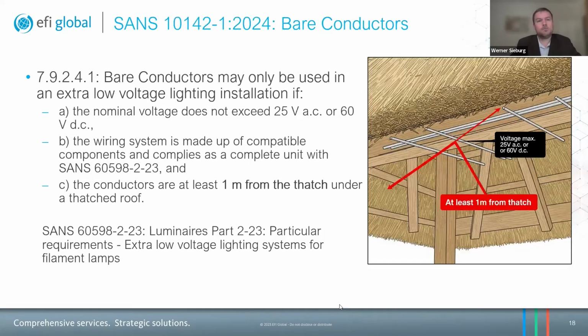All right, thanks, Kashan. So 7.9.2.4.1, it's quite a long sequence of subclauses. Bare conductors. Now, a bare conductor is basically a completely uninsulated conductor. I just want to place this in context. I think it's the last 15, 20 years, not as much anymore, but where conductors are actually spanned from one end of the room to the other end. And it's actually because they're above ground and because direct access there from a person is not really likely.